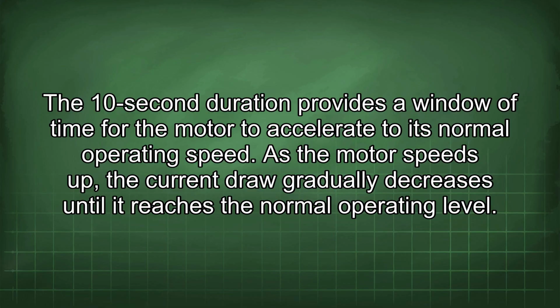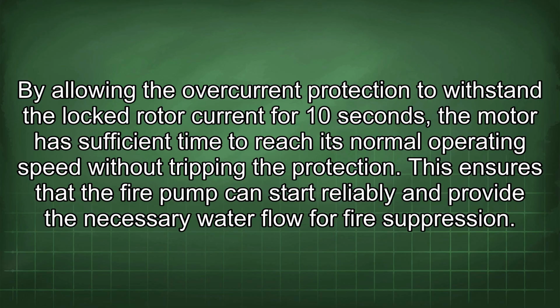As the motor speeds up, the current draw gradually decreases until it reaches the normal operating level. By allowing the overcurrent protection to withstand the locked rotor current for 10 seconds, the motor has sufficient time to reach its normal operating speed without tripping the protection. This ensures that the fire pump can start reliably and provide the necessary water flow for fire suppression.